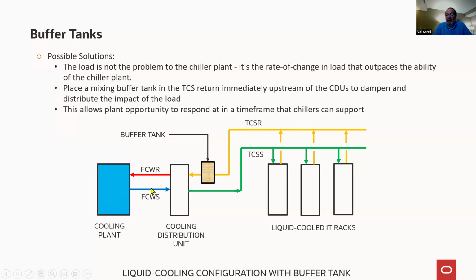The chillers eventually come back up, they restart on generator power, they restore production of cool water, and when that condition happens, you bypass the thermal storage, and as a side stream, you recharge slowly. You don't have to put a lot of flow through that thermal storage tank. So the use of thermal storage and buffer tanks is kind of really muddled, but in my context, when I say a buffer tank, I mean that it's a mixing tank in the return side of these loops, whereas the thermal storage tank is a stratified tank on the supply side of the loop.